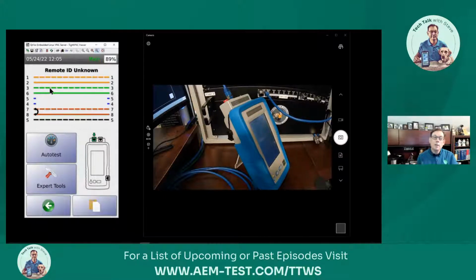The nice thing about having a live wire map is that you don't have to run an auto test to know you have an issue with the cable. Right here we see immediately we've got a short and we've got an open. If I click in the middle of my wire map, it'll run a quick diagnostic and show us the distance to the short and the distance to the open—roughly 14 meters or so to each.